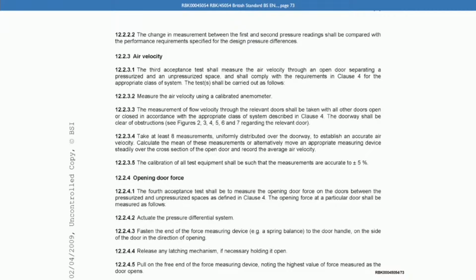Yes. As I said earlier, the anemometer we use is a vane anemometer. You've got 2 or 3 buttons on the front of it. You can press one of the buttons, scroll down, and it says select test. So you'll select test and it'll say test 1. You scroll down again, there's another take measurement, so you select it. You put the vane anemometer in front of the door, you press the button, and you put a predetermined time in, say 3 seconds. And after 3 seconds, it'll record a static number. It's not flashing. That static number is the average velocity during that 3 seconds.